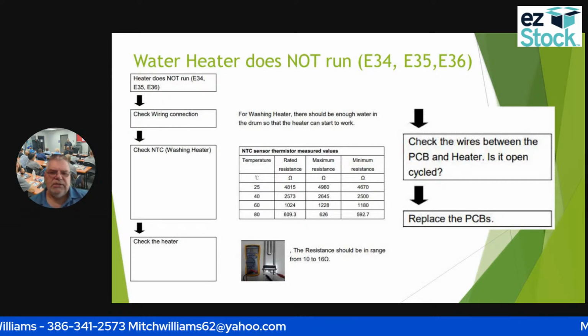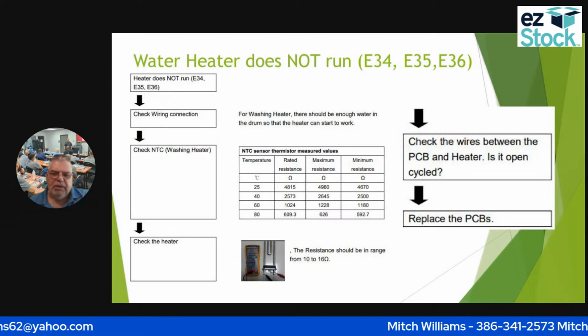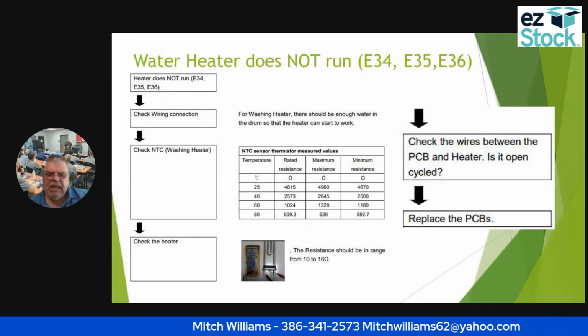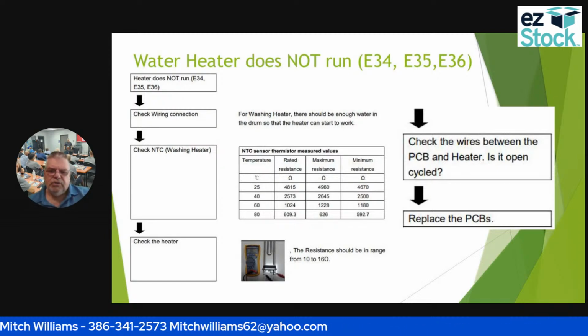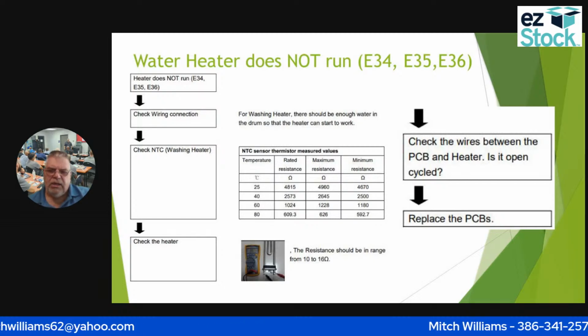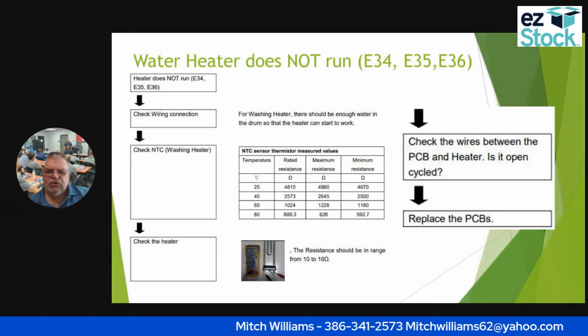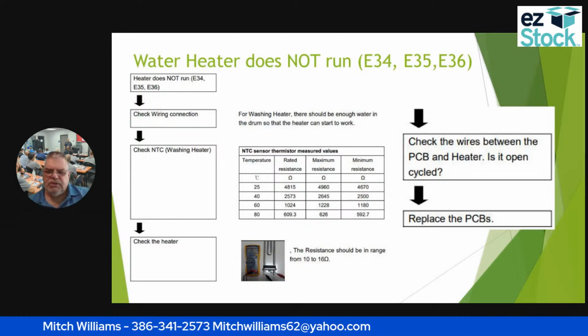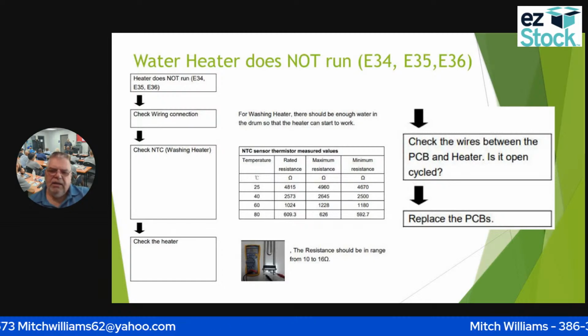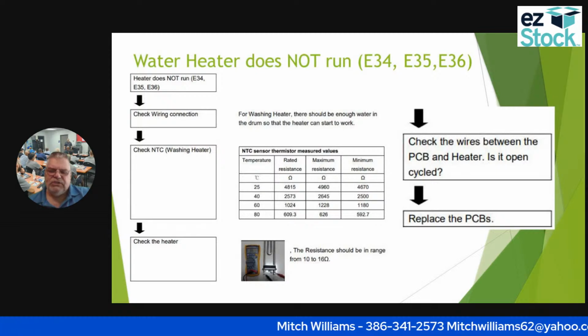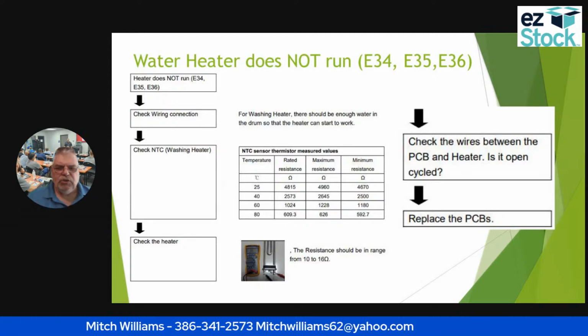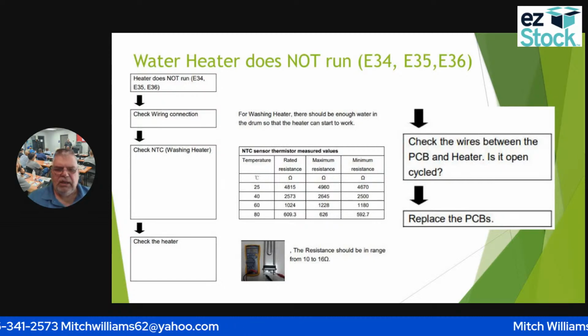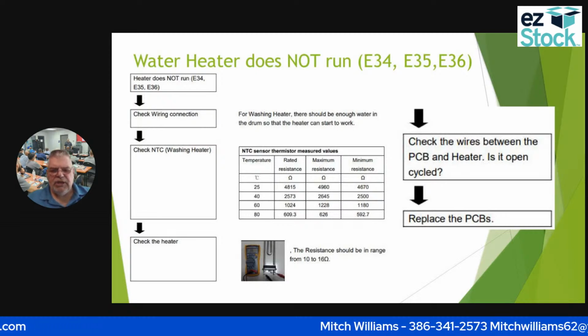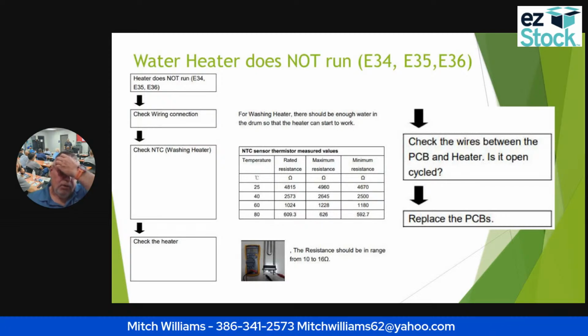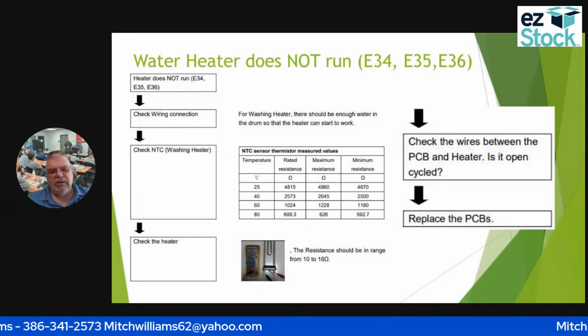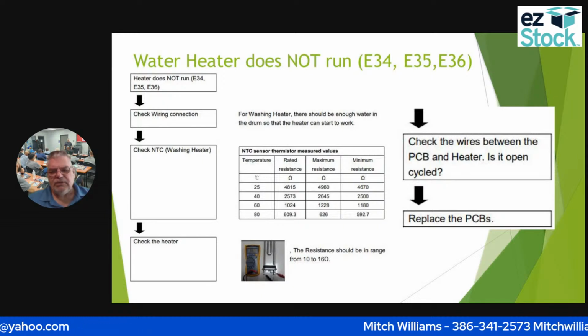So that NTC sensor, I'm going to have to find the corresponding temperature. So if I'm at 80 degrees, my resistance should be 609.3. The maximum resistance should be 626. The minimum resistance, so it's going to be somewhere between 592.7 and 626 ohms. Should be at 80 degrees, should be what I'm going to be reading for the resistance. Okay, so I'm going to check that heater. The resistance should be in range from 10 to 16. You see right there where they're checking the resistance for that heater. They have removed this from the unit.